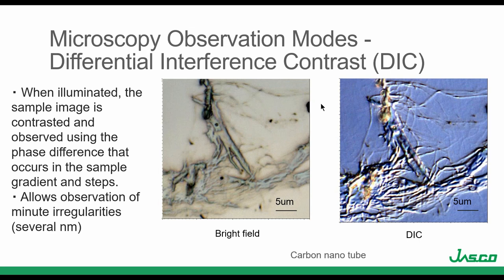The last observation mode I want to show is Differential Interference Contrast, very well known as DIC. What is really important here is that we are able to see features that don't appear under bright light. Before joining JASCO, I was working with failure analysis, and this observation mode was very useful when trying to find contamination in printed circuit boards. Sometimes in bright field I couldn't find any sign of contamination, and dark field showed nothing either. But using DIC mode was when I could find the features I was interested in.